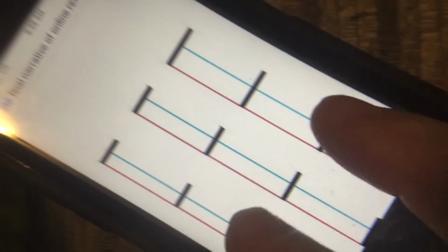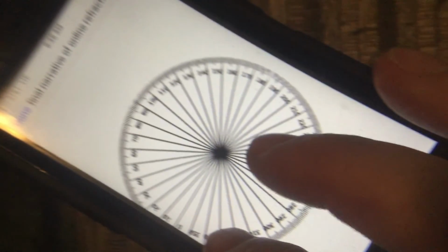Now we're moving back to our neutral position for astigmatism axis, where the red and blue lines are in perfect focus and at their widest. And we want to measure astigmatism axis to get it in degrees. We do this by scrolling down to the astigmatism target, which if we expand it to make it an easier measurement, we can now place a ruler exactly vertical to us through the center of this astigmatism target.